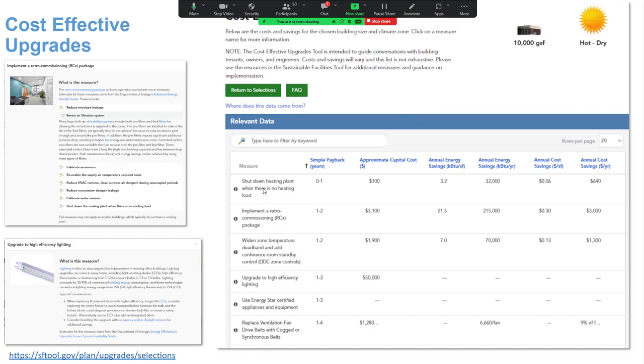We list all the things you can do that are cost effective in 10 years, ordered by how fast their simple payback is, and we talk about them in plain English. The first item is shutting down the heating plant when there's no heat load. The second is implementing a retro commissioning package — something more complicated that might pay for itself in one or two years. You click on it and we unpack it, listing components from reducing envelope leakage to calibrating air sensors. Anywhere there's an arrow in SF Tool, you can click to get more information.